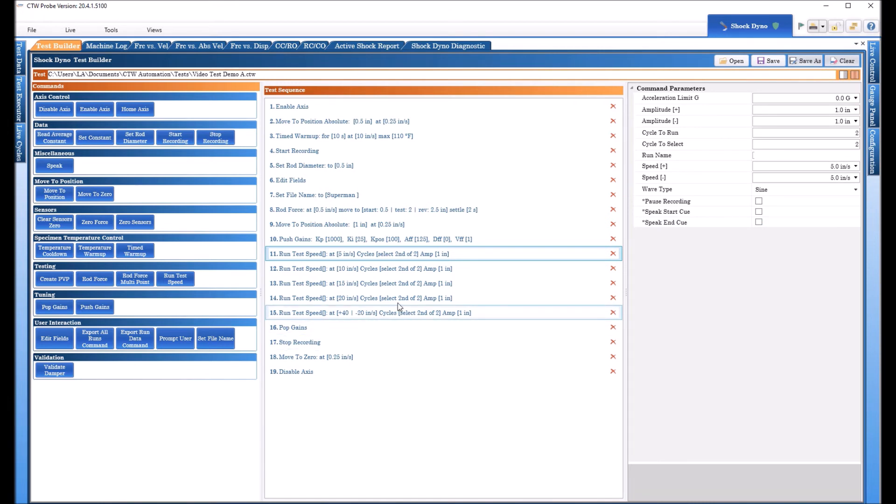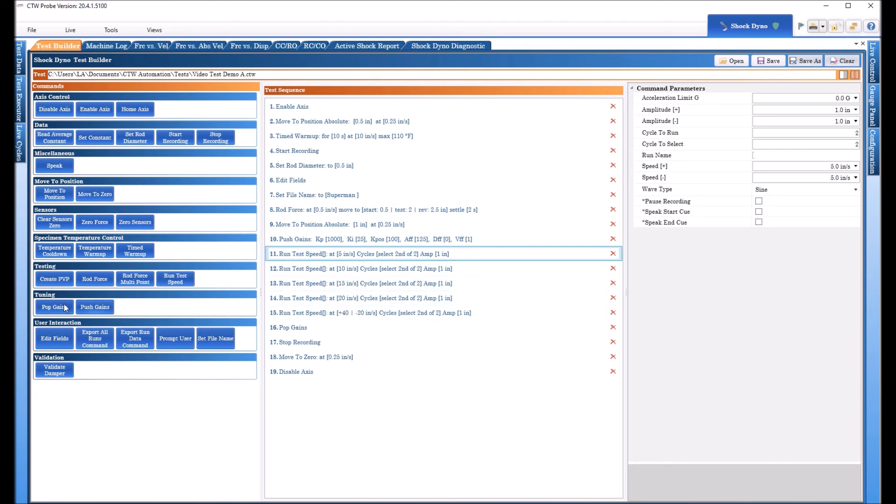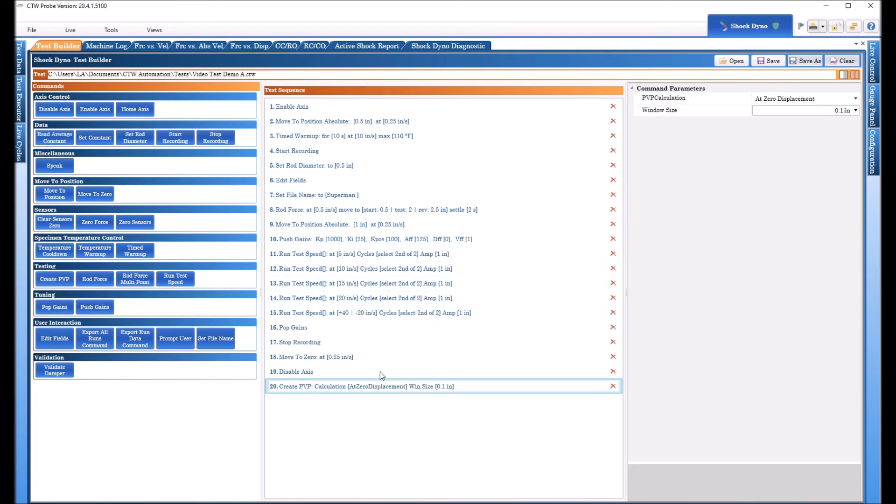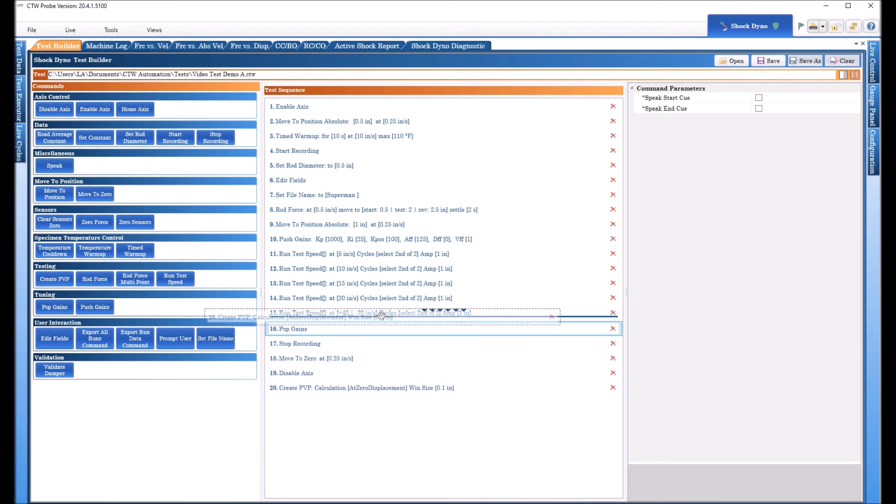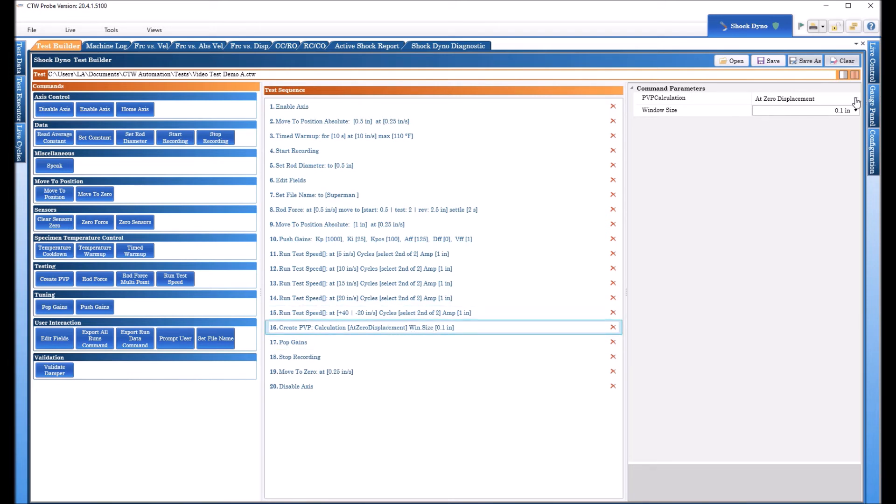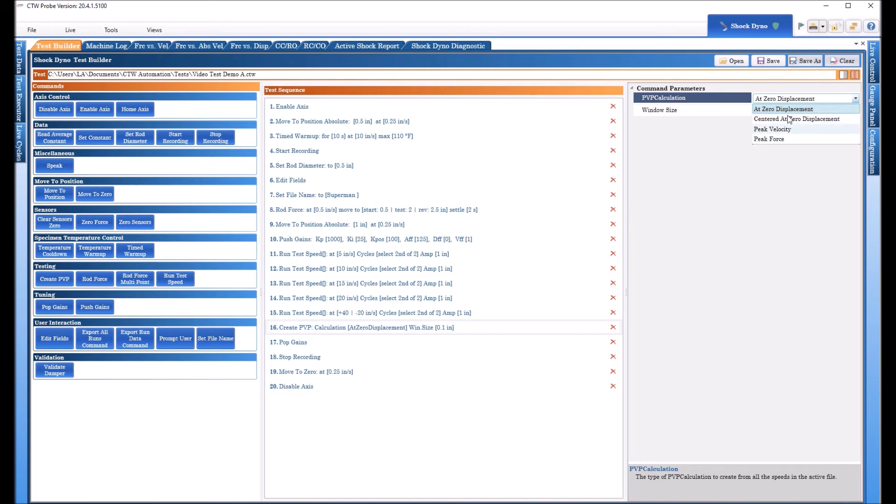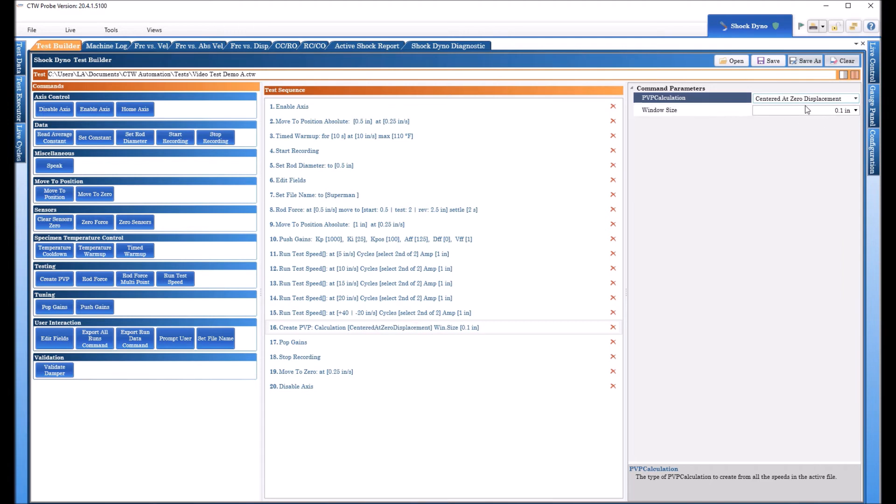Now the other thing we can add to this test that many of you use is a PVP so you no longer have to create individual PVP tests. If you have any series of speeds if you do create PVP command you can just add it to your test and all of a sudden you've taken a multi-speed run and created a PVP from it. So you get your PVP you come over here and you have three real options. You can use centered at zero displacement or peak velocity or peak force.